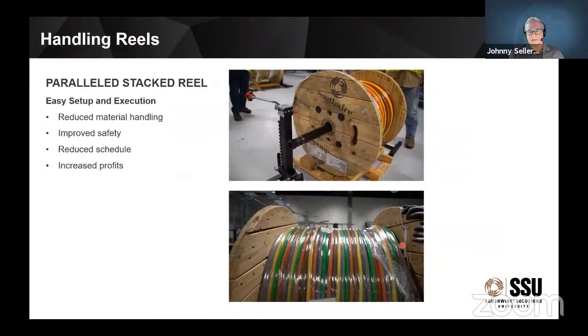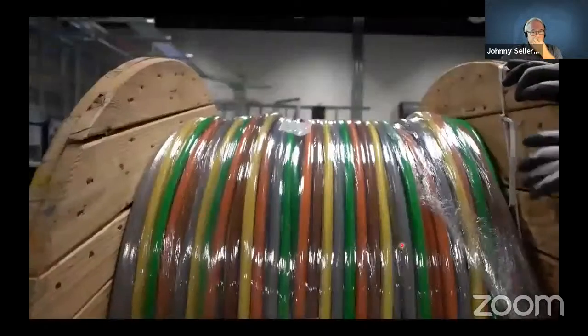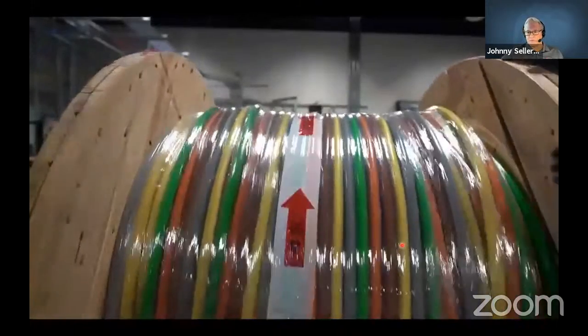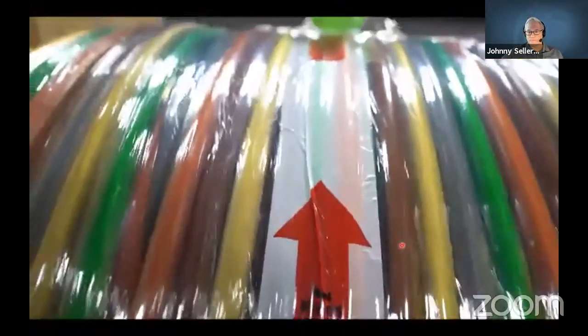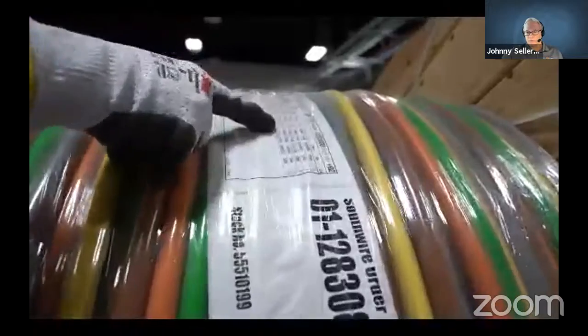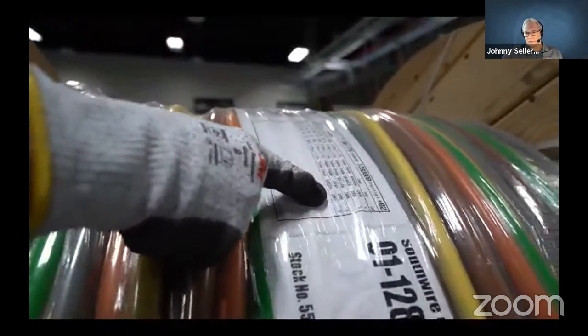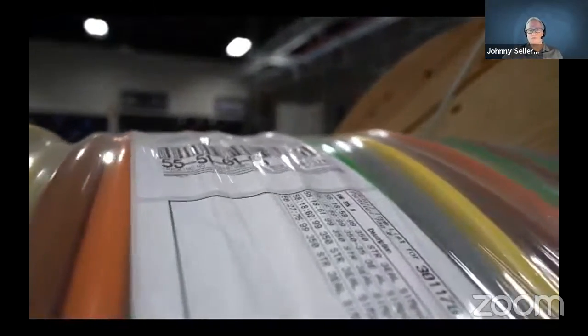When we build these reels and they're paralleled and stacked, they get bigger and heavier, but we reduce material handling and increase safety — no back injuries. The schedule improves: instead of maybe a week to do pulls, you can do it in a day. Instead of a week with five or six people, you do it in a day with two people. That turns directly into bottom-line profits and reduced schedule. These parallel reels come out shrink-wrapped with directional arrows, so you don't have to guess which way to position the reel — you'll know which way the heads are installed and how it comes off.